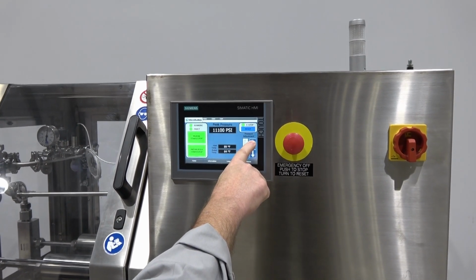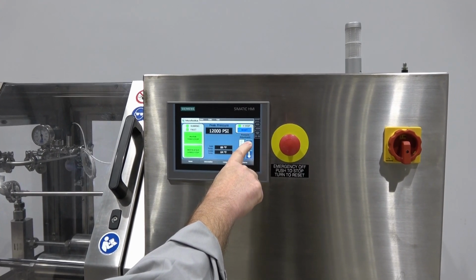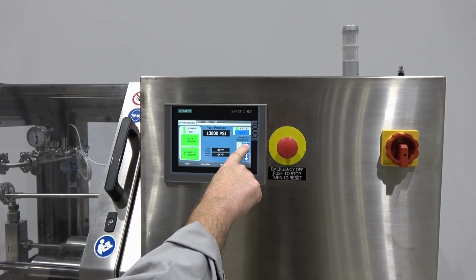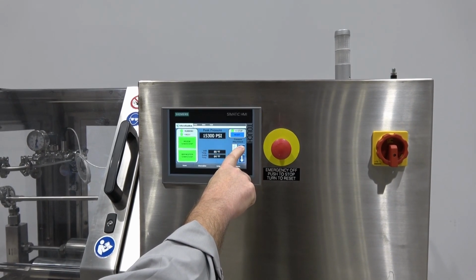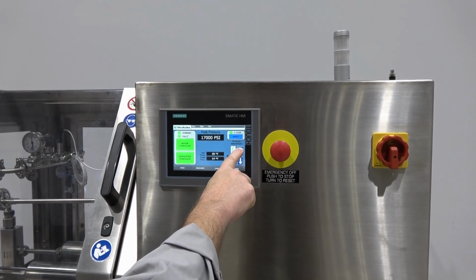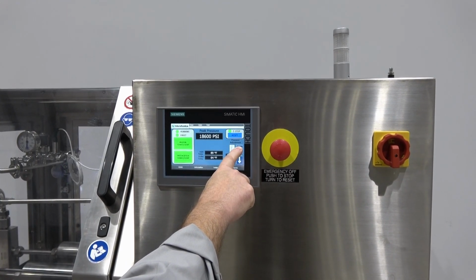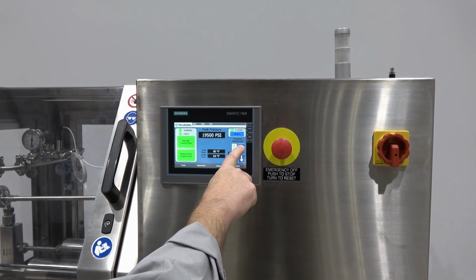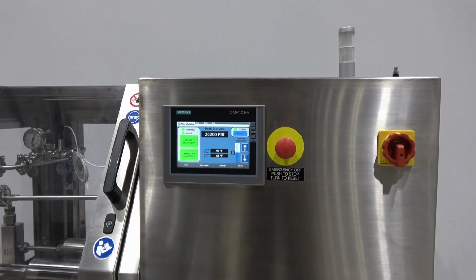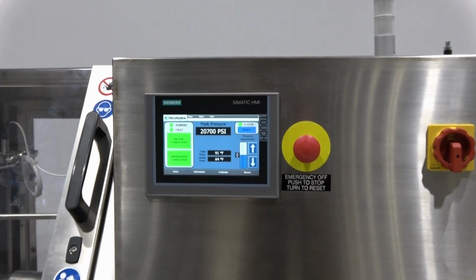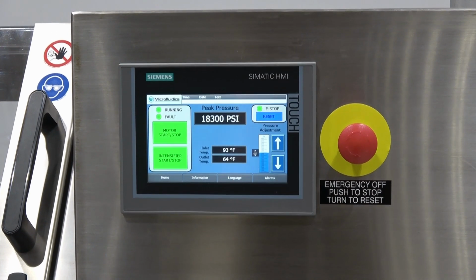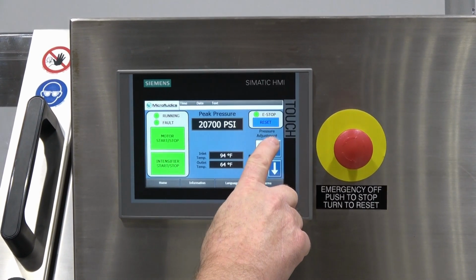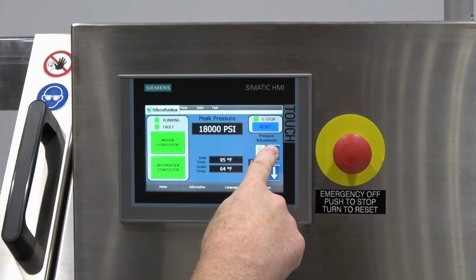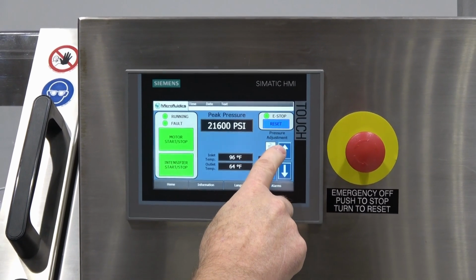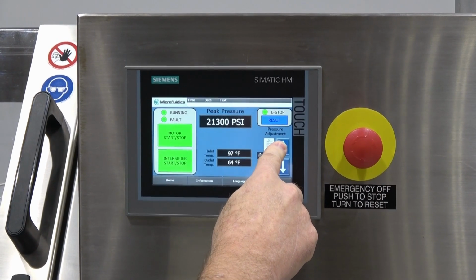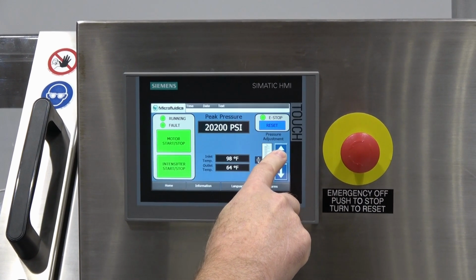Easy swap, just swap those two thermocouples around there. So you can see the temperature is climbing. That means we're getting a lot of interaction going on and a lot of friction, which generates heat and causes the temperatures to rise. And that's the reason you need a chiller hooked to it, and I'm only going to run this at 20,000 right here. Because of the interaction chamber setup with the 5-channel, it's more made to run at lower pressures. And run it on up a little bit more here.